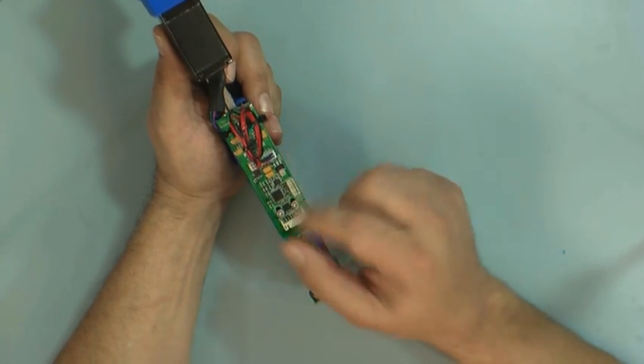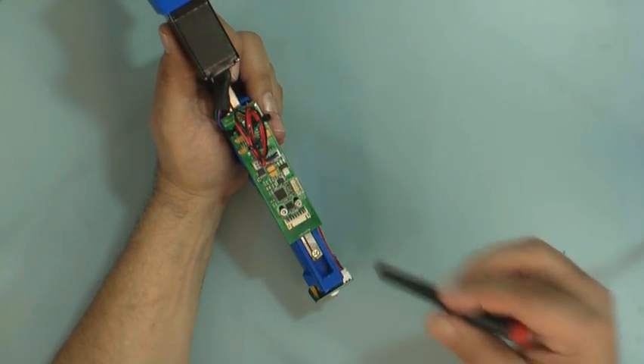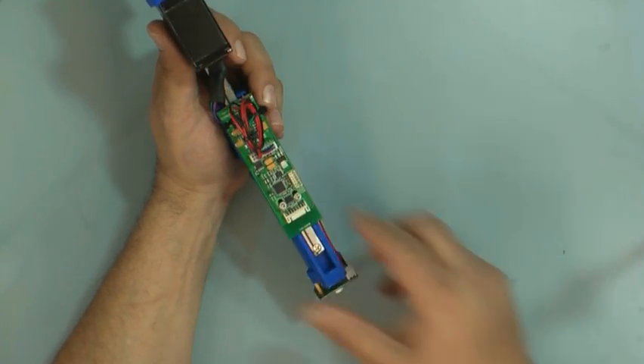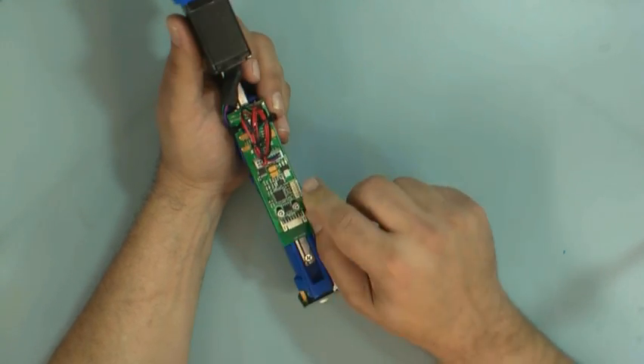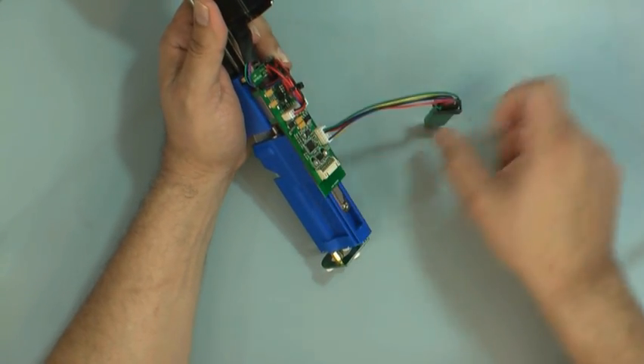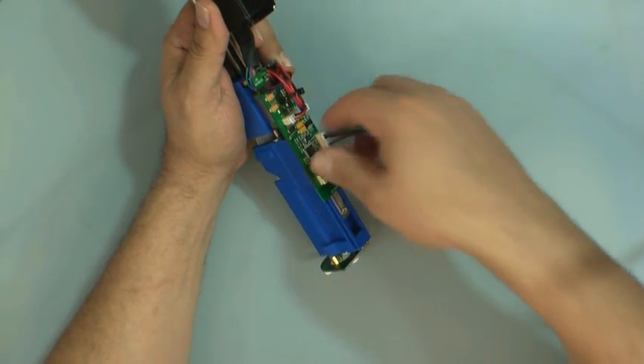Your circuit board here, you've got the same three millimeter screws. Take a two and a half millimeter hex driver for adjusting the positioning if you have to adjust how it sits. The programming port here for your ST-Link. If you have to do a firmware update, you would flash it with your ST-Link.